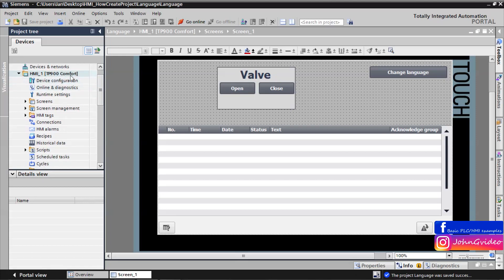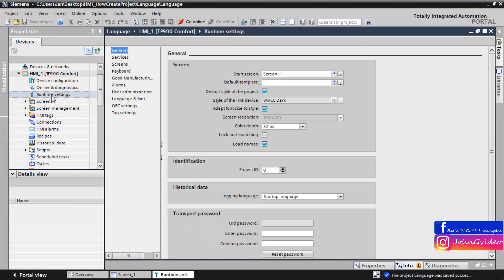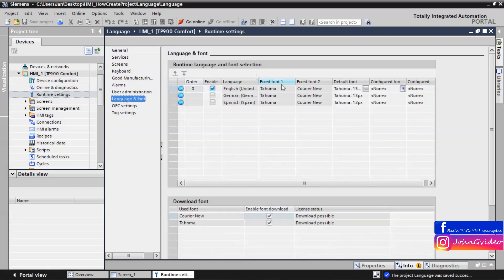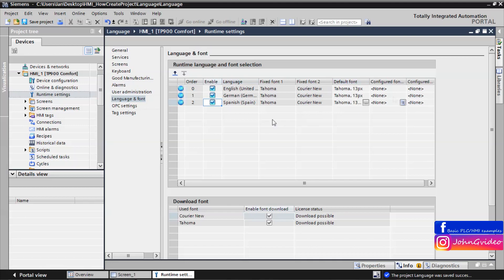Open the HMI project, click on 'Runtime Settings', and click on the option 'Language and Font'. Here we have all project languages. If you want to enable these languages in your HMI, just click on the enable checkbox. Now we enable German and Spanish in your HMI. Here you can also define the fonts for these languages and set the default font. Save the project.